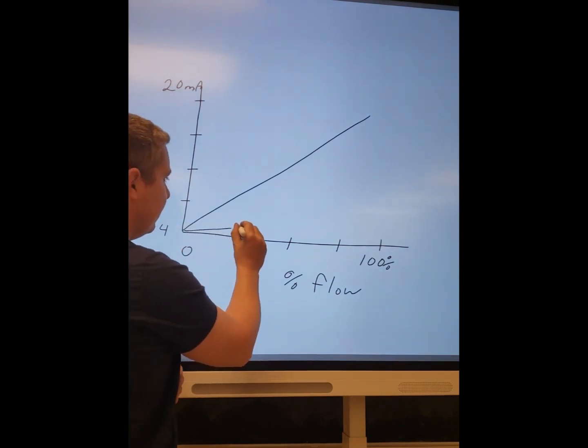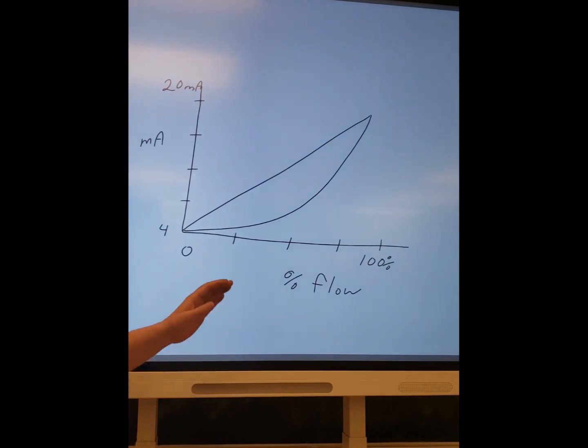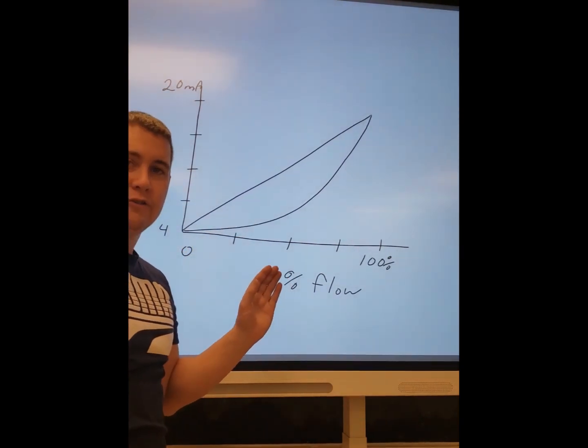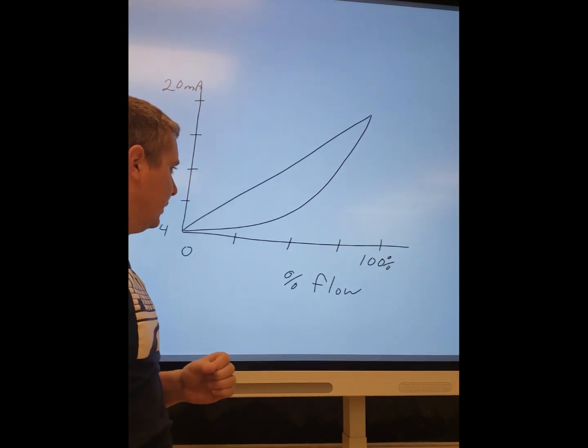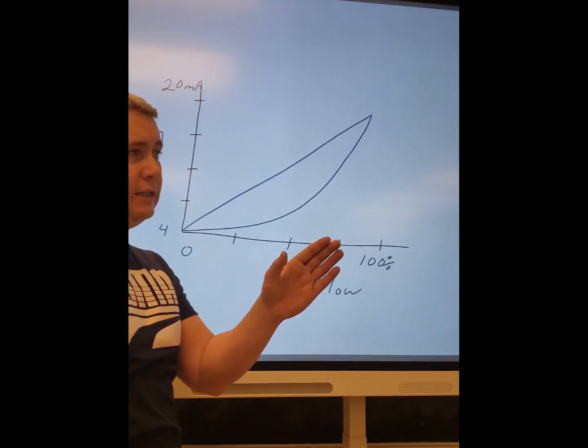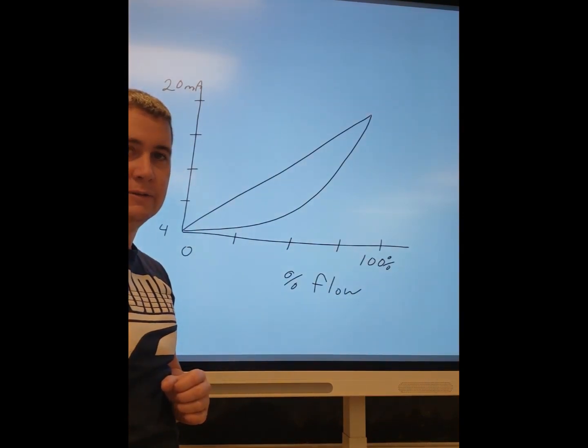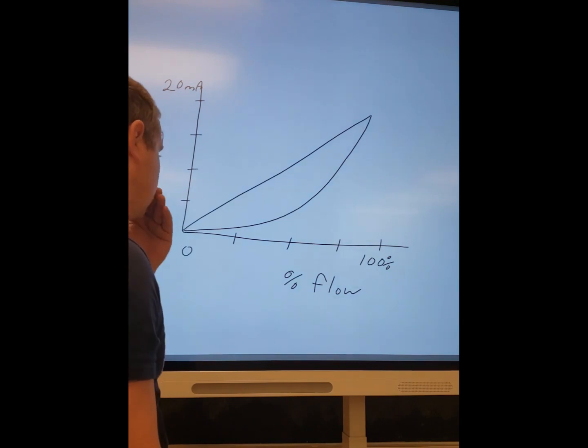But in reality with flow, because flow is not linear, we got a square rooted output. This is the natural curve of flow, flow is naturally square rooted, and so in order for us to then have a linear output we have to use a square root extractor output.